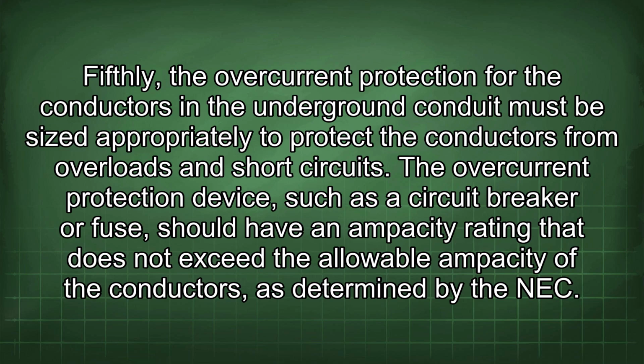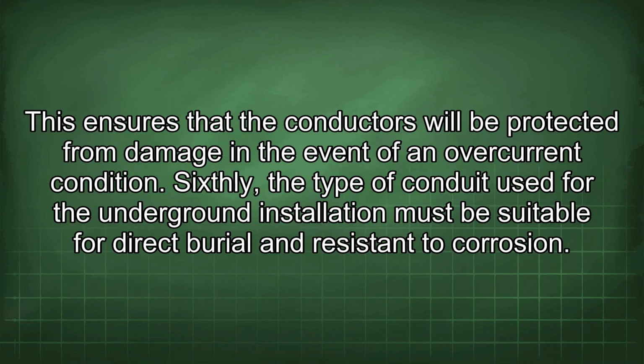Fifthly, the overcurrent protection for the conductors in the underground conduit must be sized appropriately to protect the conductors from overloads and short circuits. The overcurrent protection device, such as a circuit breaker or fuse, should have an ampacity rating that does not exceed the allowable ampacity of the conductors, as determined by the NEC. This ensures that the conductors will be protected from damage in the event of an overcurrent condition.